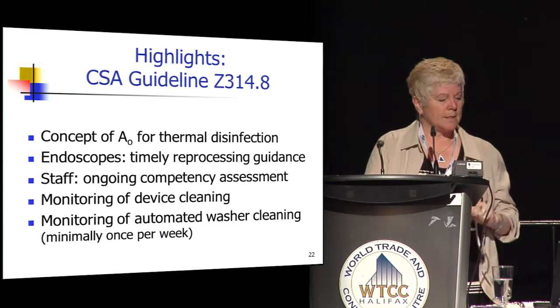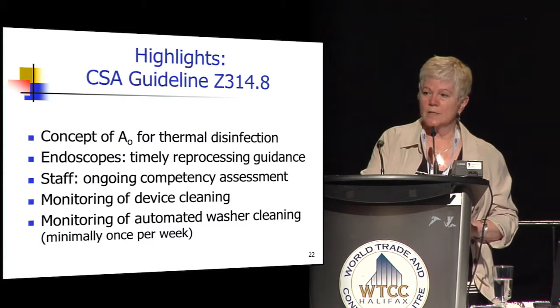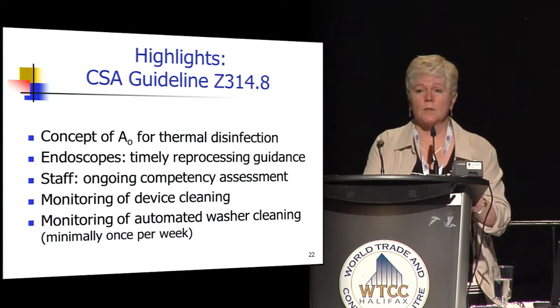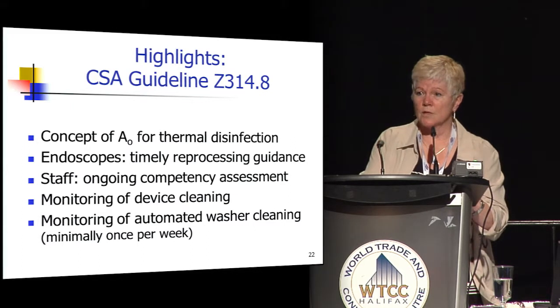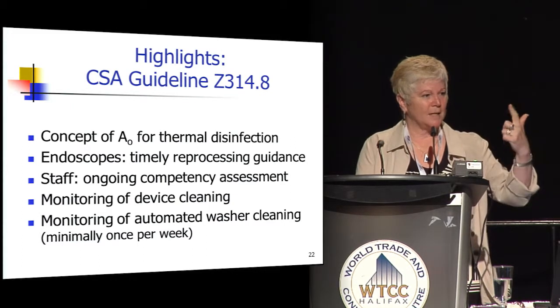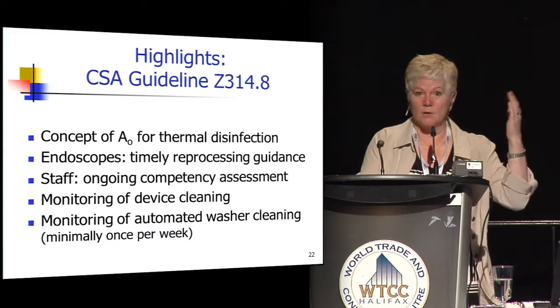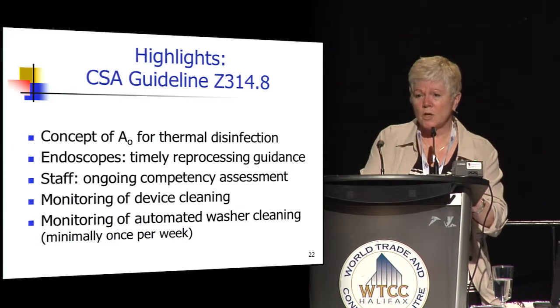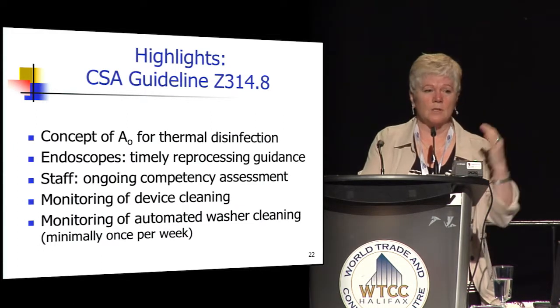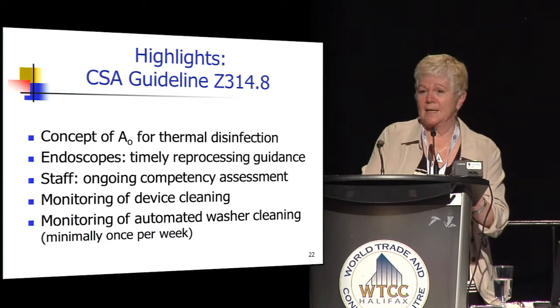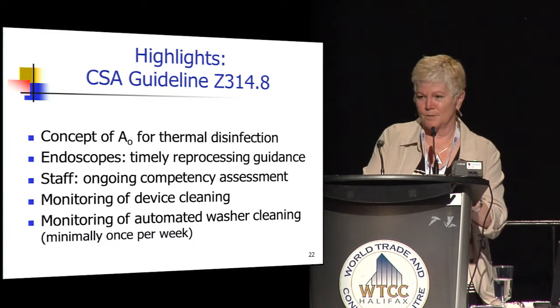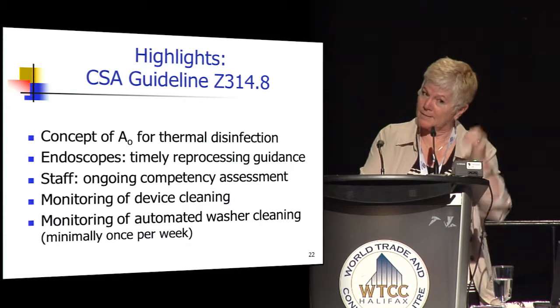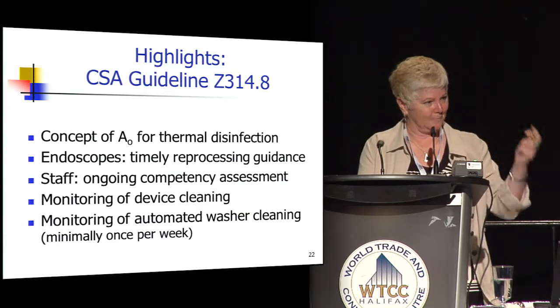And then the other is the monitoring of automated washers. I don't know about you, but 10 years ago, nobody was monitoring their washers. So as long as the water ran, the lights came on, and you could hear noise, those washer disinfectors were used until they virtually died. They may not have been doing anything in terms of washing stuff off of the instruments, but the water came in, the lights went on, and it ran a cycle.